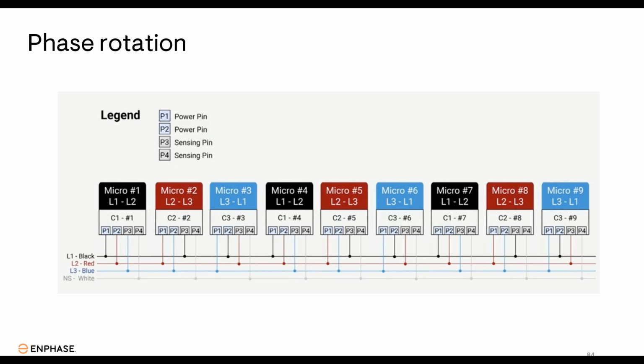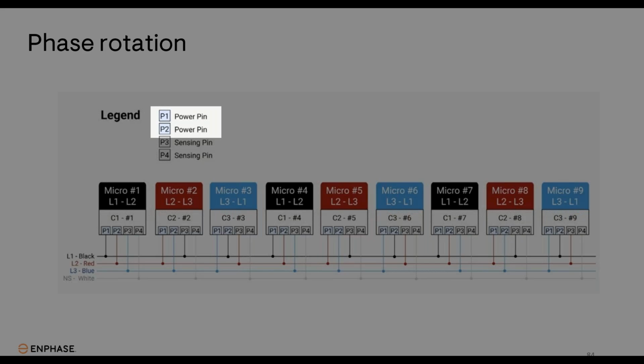There are four pins in the microinverter: the first two are power pins, the second two are sensing pins. In this diagram, the first microinverter plugged into the first connector puts power onto line 1 and line 2, and senses on 3 and 4. The second puts power onto line 2 and line 3, sensing on 1 and 4. The third puts power onto line 3 and line 1, sensing on line 2 and 4, and so on down the line. That's how you get ideal phase balancing and rotation from the microinverters.